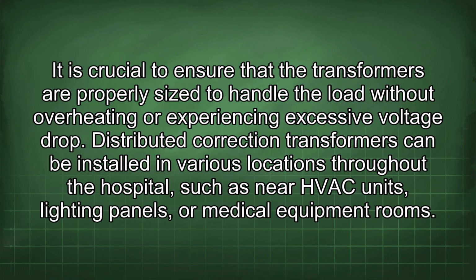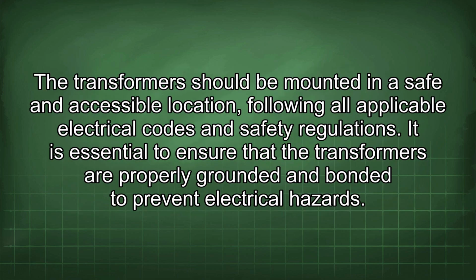It is crucial to ensure that the transformers are properly sized to handle the load without overheating or experiencing excessive voltage drop. Distributed correction transformers can be installed in various locations throughout the hospital, such as near HVAC units, lighting panels, or medical equipment rooms. The transformers should be mounted in a safe and accessible location, following all applicable electrical codes and safety regulations. It is essential to ensure that the transformers are properly grounded and bonded to prevent electrical hazards.